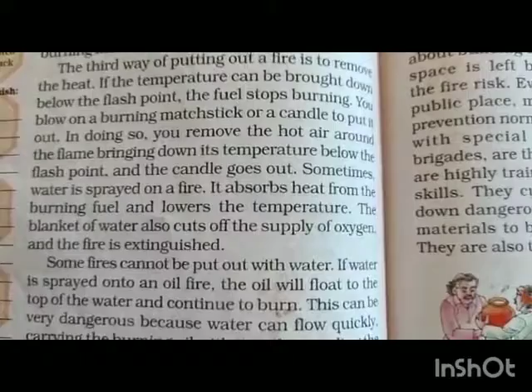Some fires cannot be put out with water, so you have to be very careful. If water is sprayed onto an oil fire, that is very dangerous. The oil will float to the top of the water and continue to burn because it is less dense than the water. This can be very dangerous because water can flow quickly, carrying the burning oil with it and spreading the fire. So never use water when oil is burning.